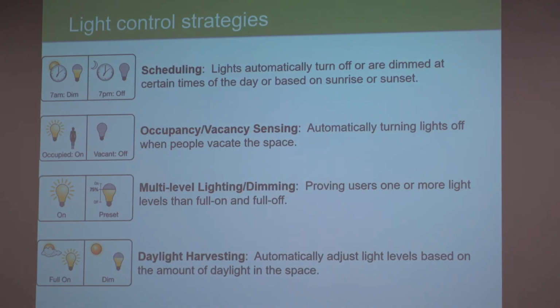Let's look at some key light control strategies for commercial buildings. There's scheduling. This is where you schedule lights, say at night, to sweep off after operating hours. That's typically done with what they call a time clock. Technically it's really a time switch, or an astronomical time switch, so it doesn't necessarily do it just by time of day, but can do it by astronomical events like sunrise and sunset.